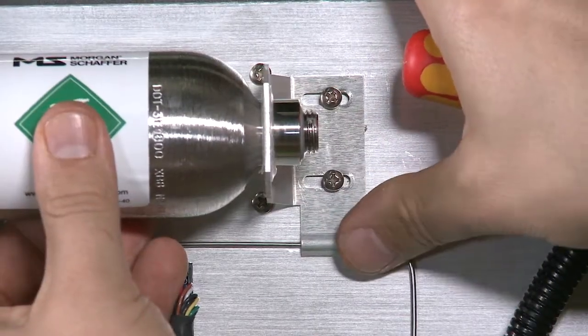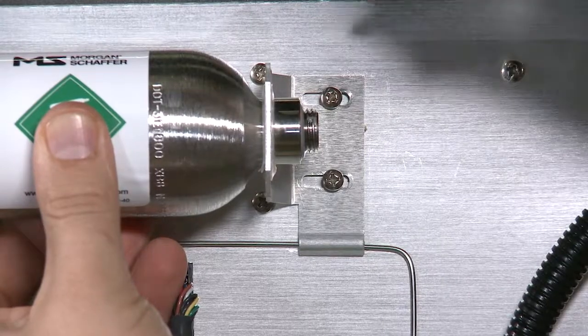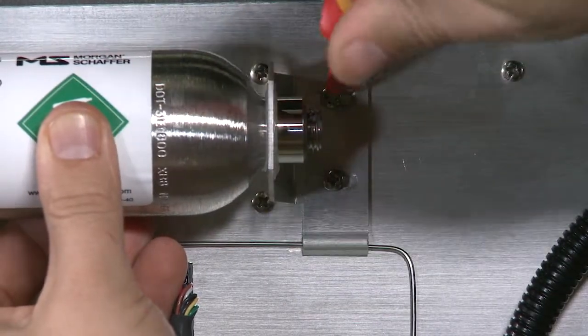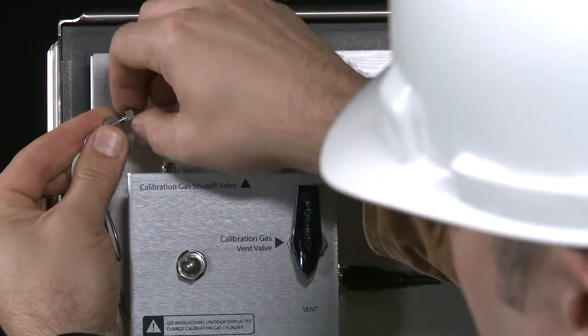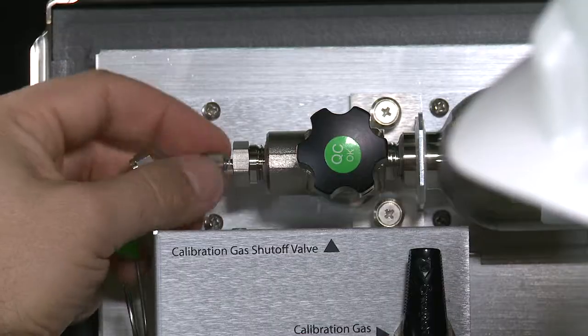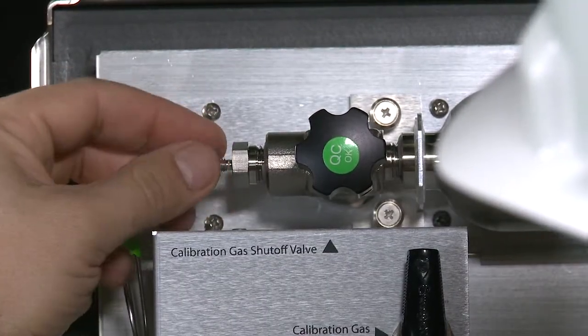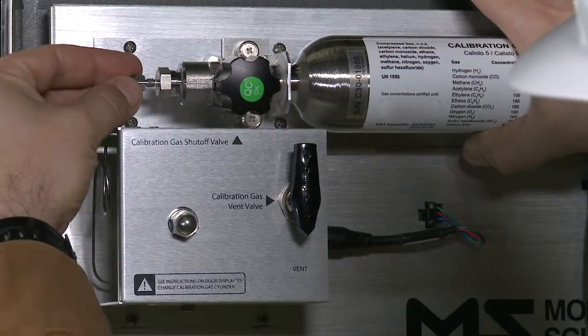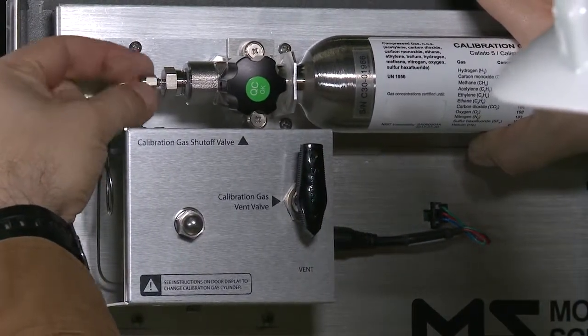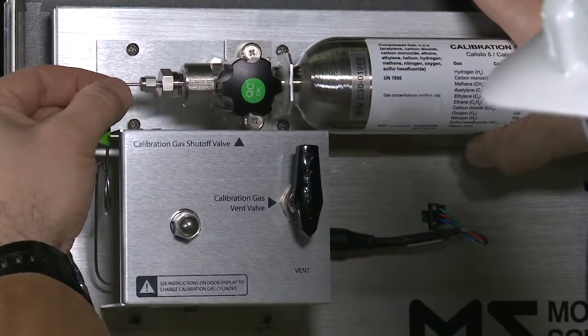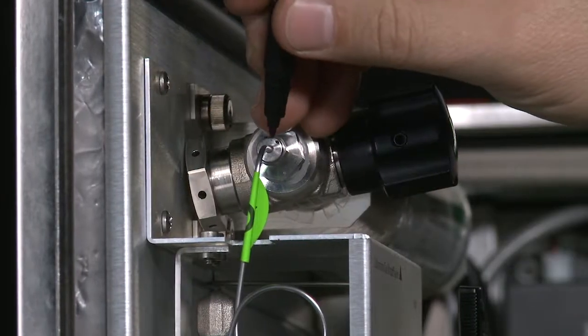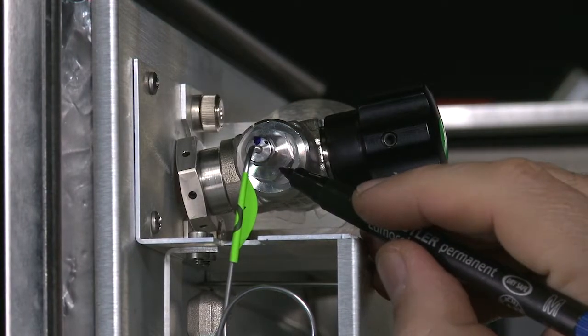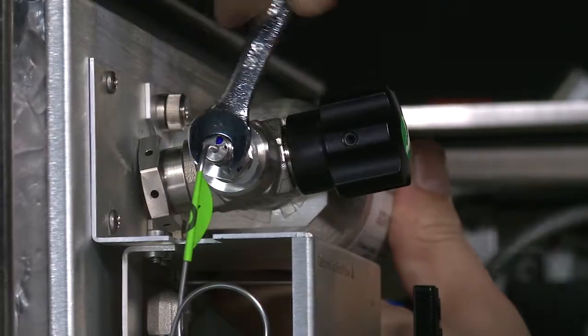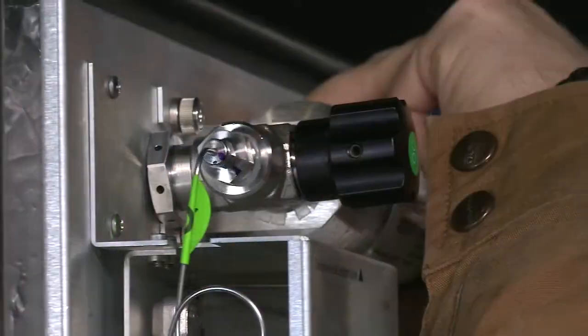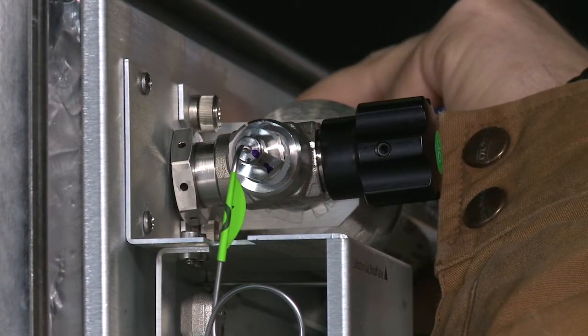Adjust the cylinder retainer so that it holds the cylinder bottom properly. Then tighten the 2 screws using a Phillips No. 2 screwdriver. Remove the plug from the tube and the cap from the cylinder. Finger tighten the tube nut to the calibration gas cylinder fitting. Use a 5/16" open-end wrench to tighten the cylinder fitting by 3/8 of a turn.